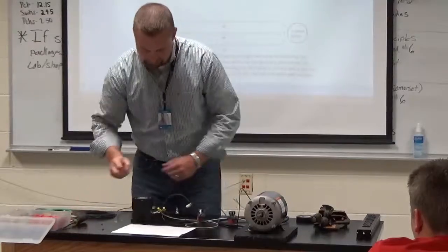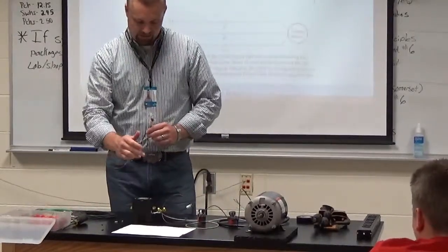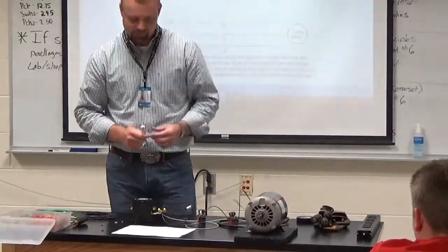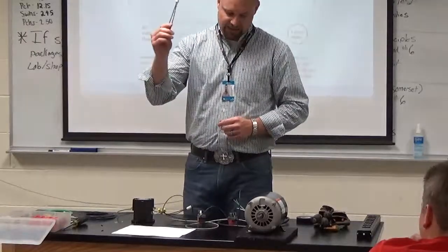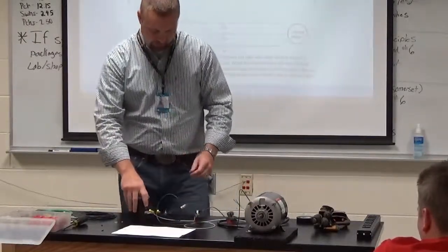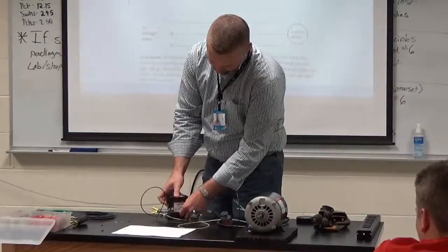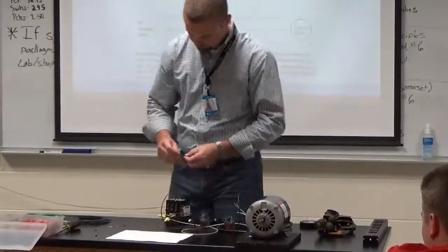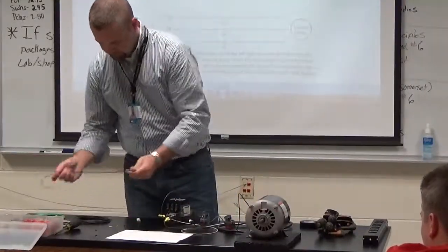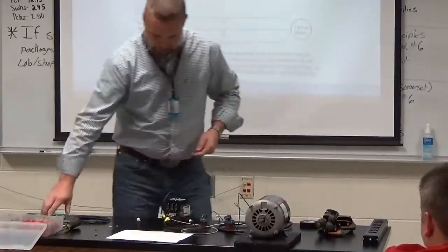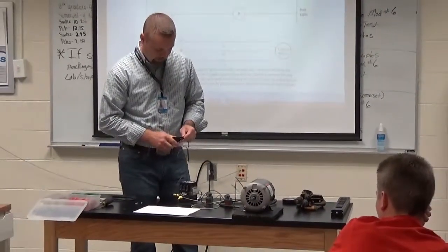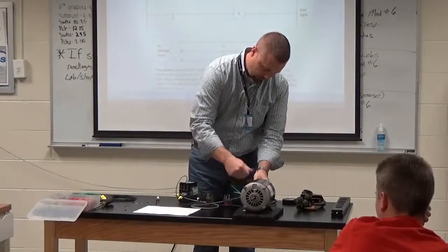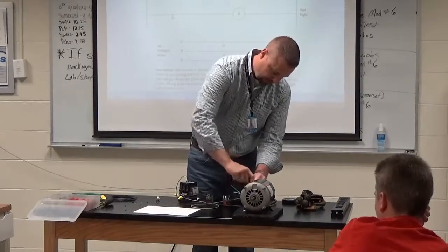Now, I want a light to indicate whenever I hit the stop button and the starter stops. I want a red light saying, hey, that motor is not running. To do that, I'm simply going to use my red light and connect it on the auxiliary contact block again. But now, instead of using the opens, we're using the closed, okay? Good. So to do that, as you see on the schematics I gave you, I'm going to run a power wire directly from power over to a closed on that auxiliary contact block.